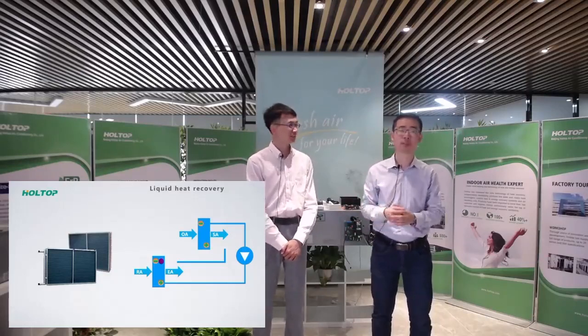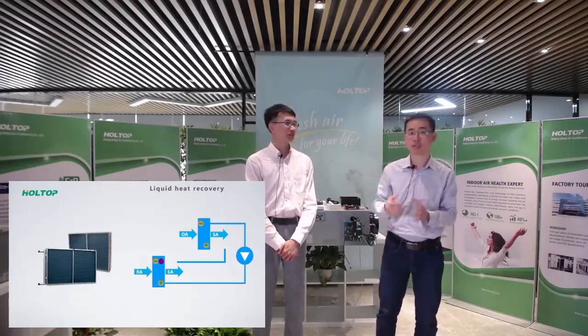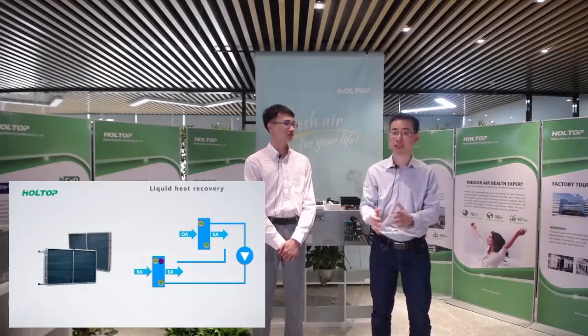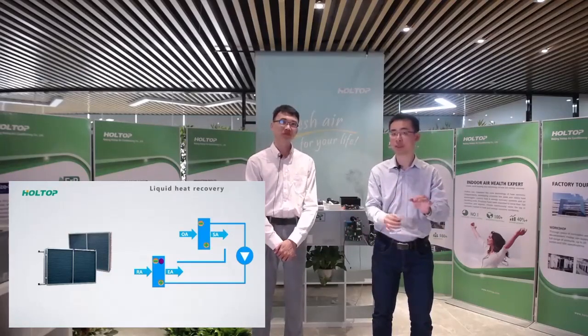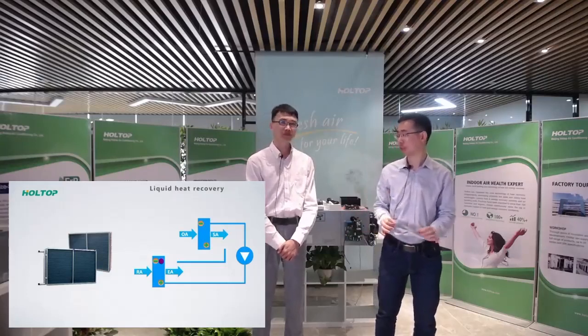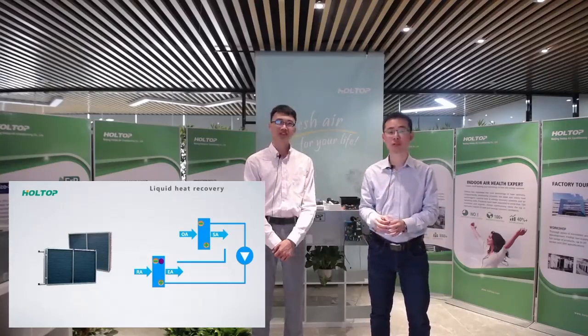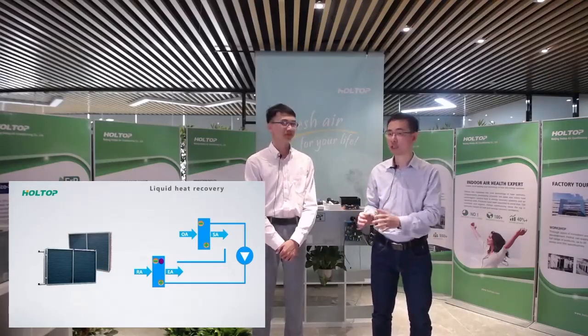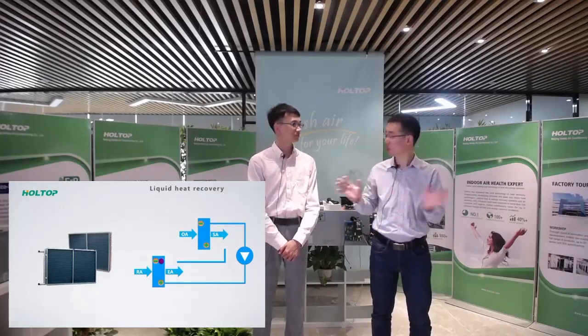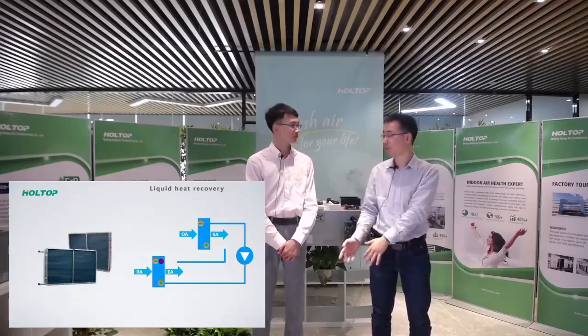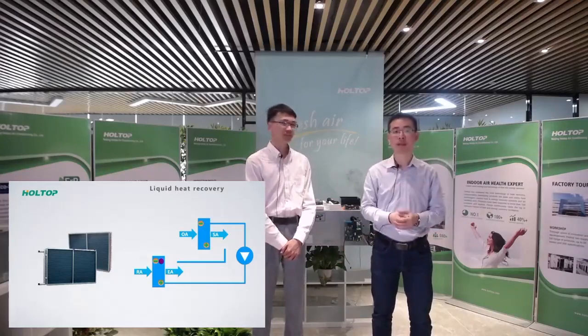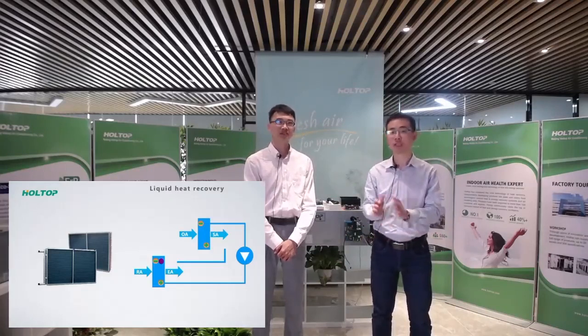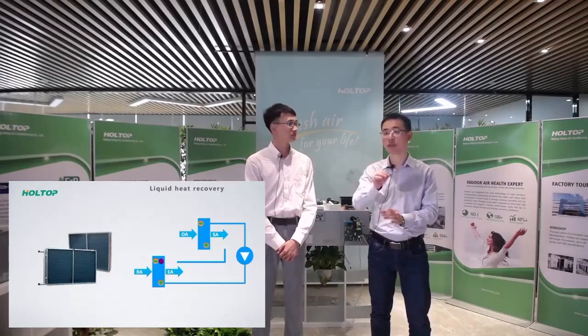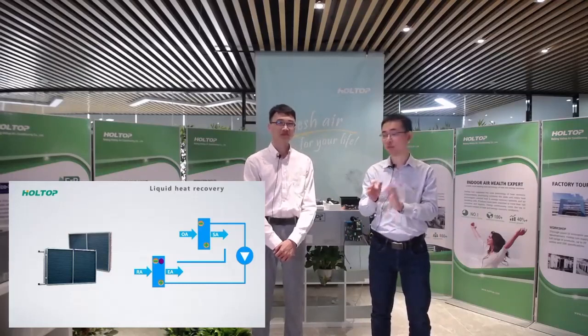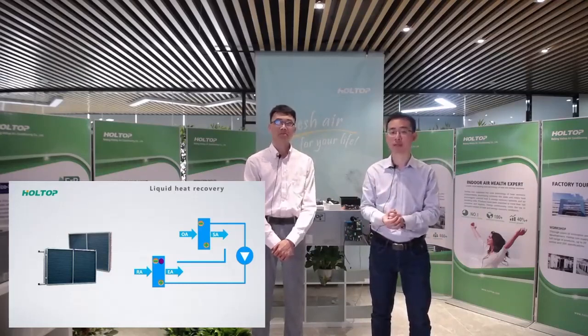And the key feature for this liquid heat exchanger is that the fresh air and the exhaust air are not in the same direction, and there's zero cross-contamination. The fresh air and the exhaust air systems are not limited. I mean, one can be on the ground floor, the other one on the rooftop. And finally, the surface of the heat recovery heat exchanger is coated with an organic resistant coating, which is anti-bacterial.